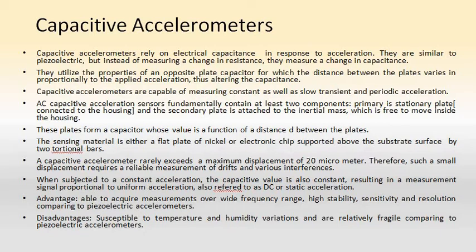That is, the variation in capacitance will be obtained as an output as a voltage signal. That is, the voltage output will be proportional to the variation in capacitance, which in turn is proportional to the variation in acceleration. Therefore, we can say the voltage output is proportional to the acceleration or the vibration.